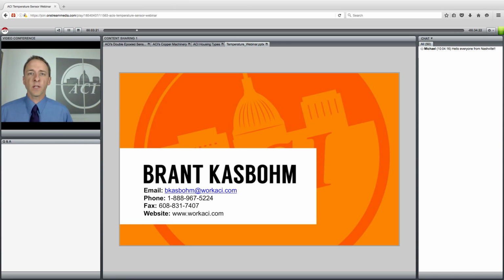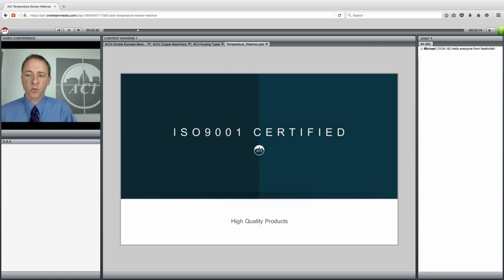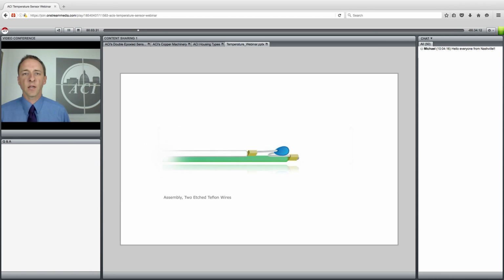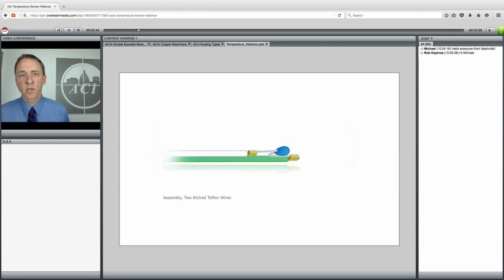So we're going to get started today by going through the process that we use to build, manufacture and assemble our temperature sensors, and this is a process that differentiates us from a lot of the other competitors out there. It starts with how we crimp the raw sensing element to the lead wires. You can see here in this slide, and I've also got one here in my hand. It's very small. These raw thermistors are very fragile, and you can see it's in blue here. And we crimp them to the lead wires, as you see here.